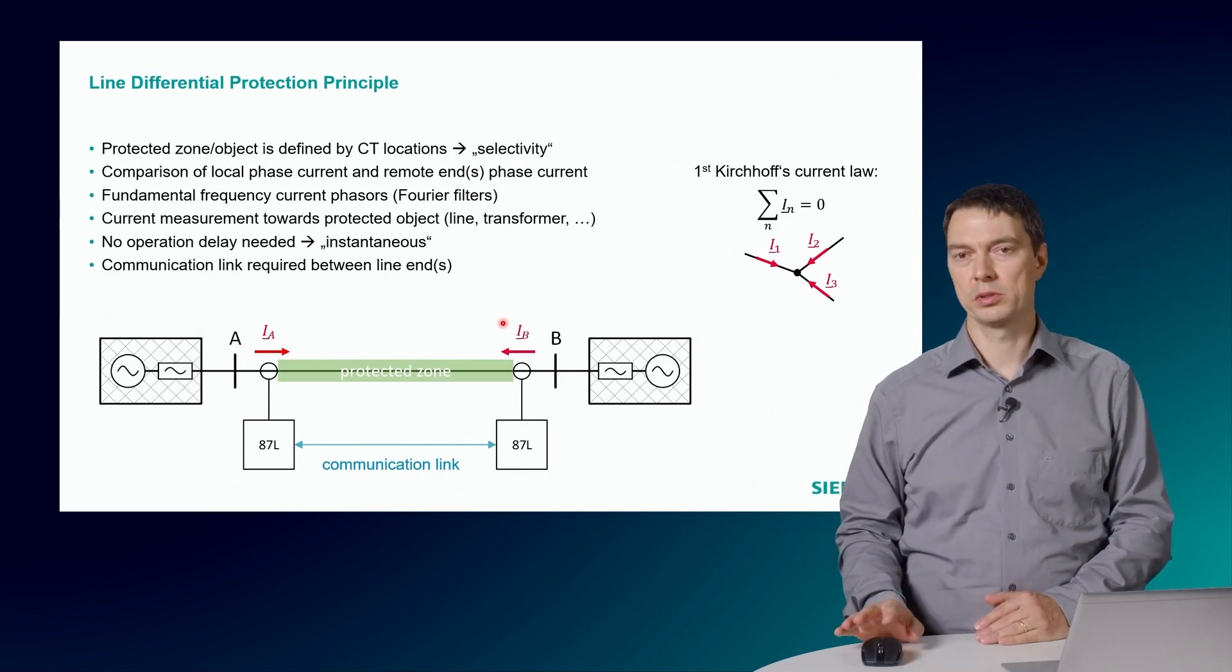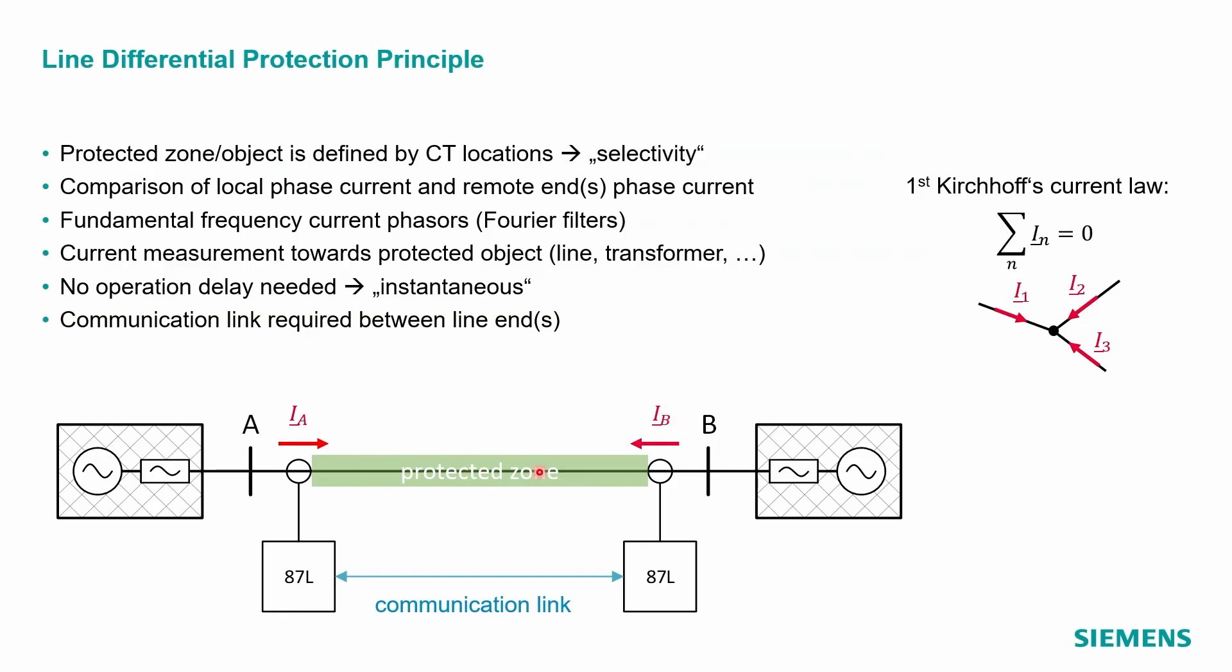The protected zone is shown in below figure here, in the green color. There we have two power grids, A and B, which are connected by a line. The current transformer locations delimit the protected zone and that gives you 100% of selectivity. The measured line currents are evaluated in the connected line differential protection devices, which are marked with the 87L, which is an ANSI code.